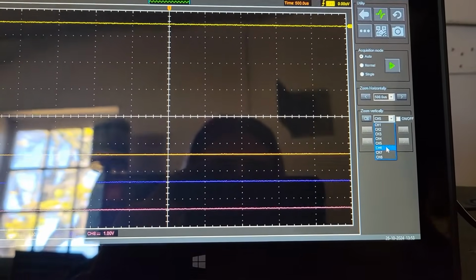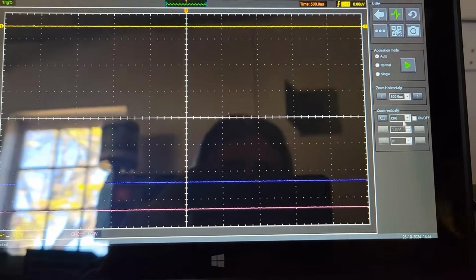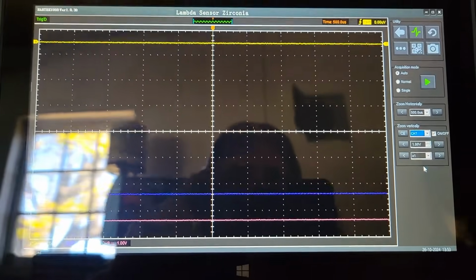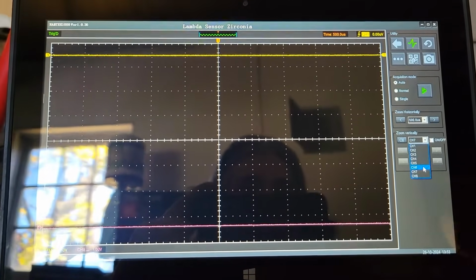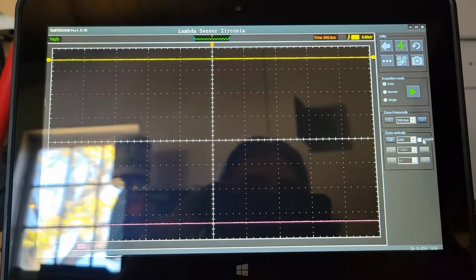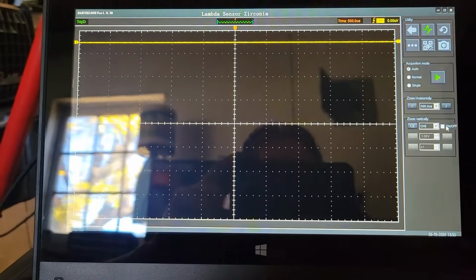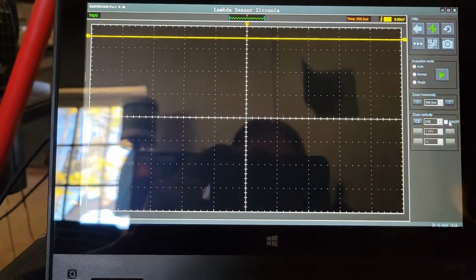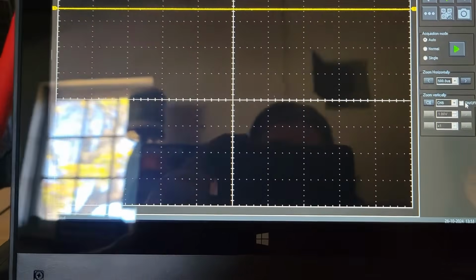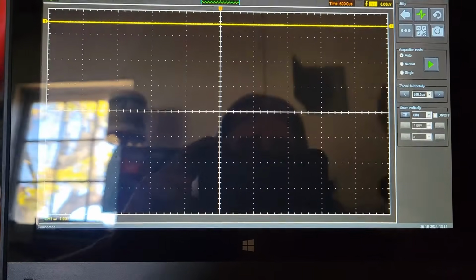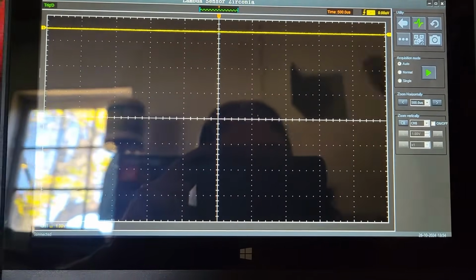They're all a little different in the way you set them up and handle them, but it's all just the buttons - it's where the buttons are. Because all we're doing is measuring voltage and time over and over again. Even if we have a sensor that translates it to pressure, flow, or amperage, we're tricking the voltage - we're tricking the scope, or using a sensor where the scope uses its voltage to give us a signal. So no matter what scope you're using, they're all going to show the same thing. It's just the quality of the image and how you set it up, where the buttons are, but you're all looking for the same thing.